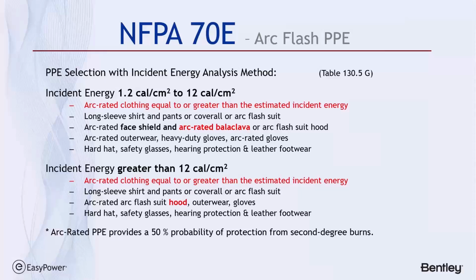Now, this last line is, again, the soapbox that I kind of revert to. If you look at the fine print on labels or the discussion from PPE manufacturers, they talk about not being able to guarantee any level of protection. And in some cases, they say it protects the wearer down to 1.2 calories per square centimeter. Well, if you recall, that 1.2 calories per square centimeter is the crossover point where there's a 50% probability of second degree burns.